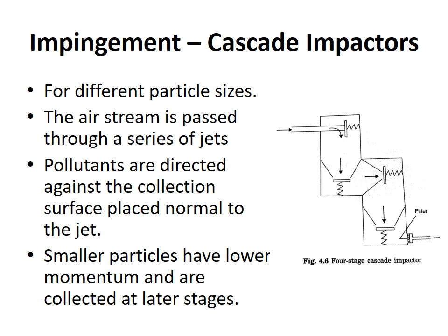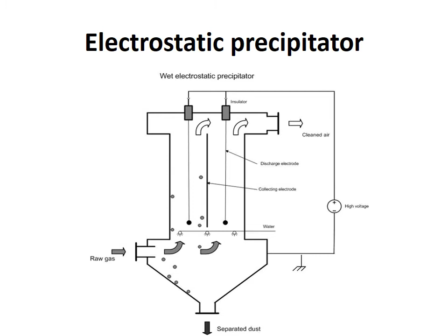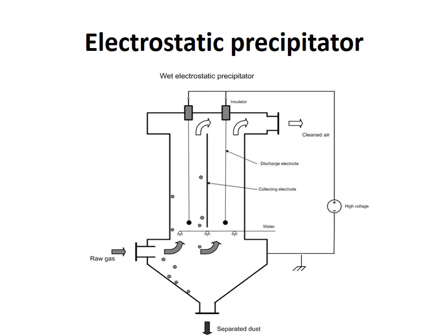Next method of sampling particulate matter is electrostatic precipitator. The most commonly used is a wet electrostatic precipitator. It consists of a discharge electrode, which is usually negatively charged, and a collecting surface or electrode, which is positively charged. In wet electrostatic precipitator, there is a provision for spraying water into the gas stream. So, the particles form a slurry and are separated from the bottom. As the raw gas moves upwards, the particles get negatively charged due to the discharge electrode and they are attracted towards the positively charged collecting electrode or collecting surface. And the collected particles are later removed from the collecting electrode.